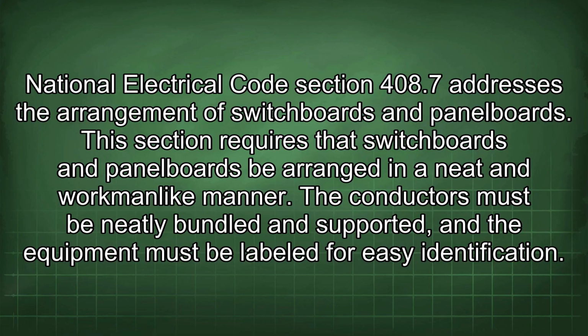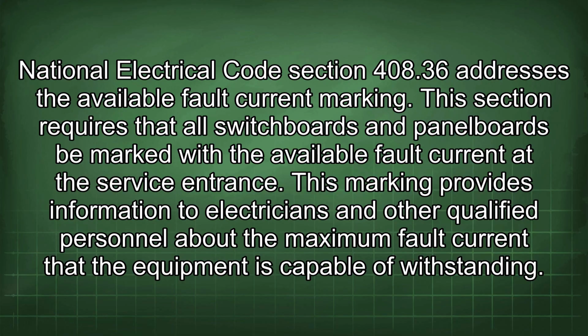This section requires that switchboards and panel boards be arranged in a neat and workmanlike manner. The conductors must be neatly bundled and supported, and the equipment must be labeled for easy identification. National Electrical Code Section 408.36 addresses the available fault current marking. This section requires that all switchboards and panel boards be marked with the available fault current at the service entrance.